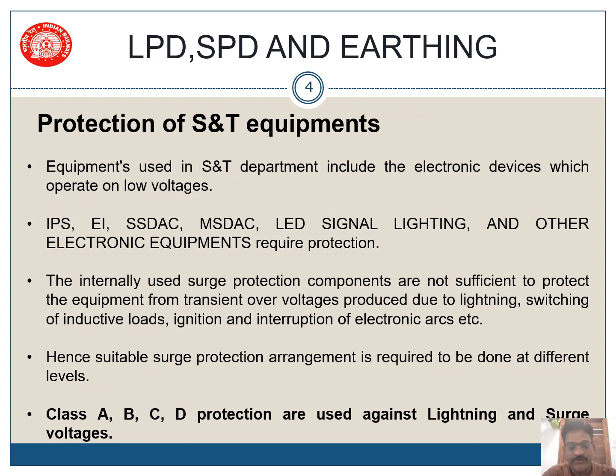Which equipments do we need to protect from lightning and surges? These: IPS, EI, SSDAC, MSDAC, LED signal lighting, and other electronic equipments used in railway signaling require protection. The internally used surge protection components, which are generally provided at the equipment level, are not sufficient to protect the equipment. Whatever surge protection devices we fit near the equipment will probably not be enough. So we need more protection from lightning and surges.